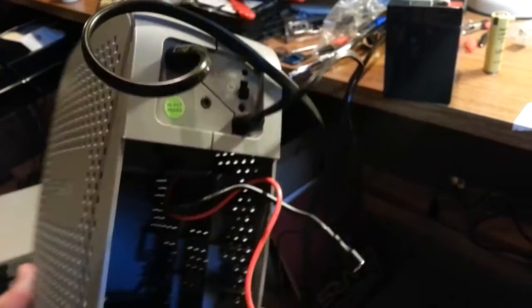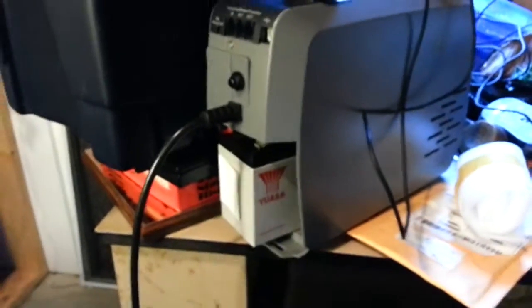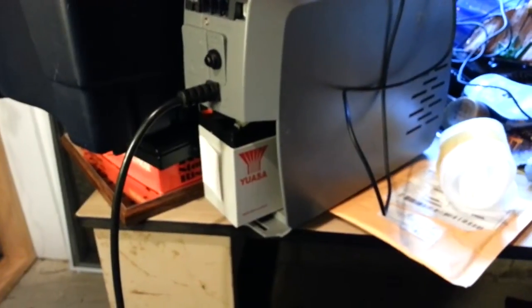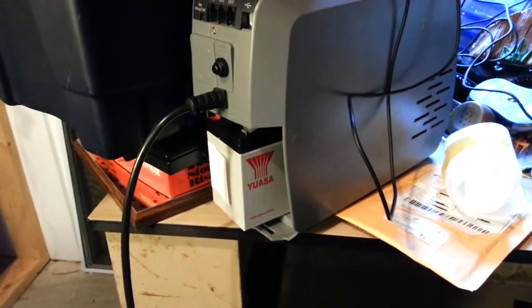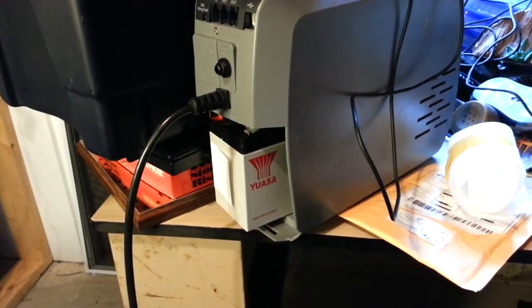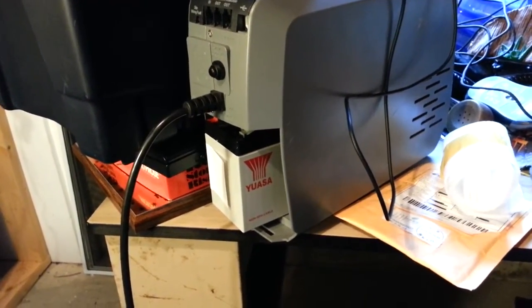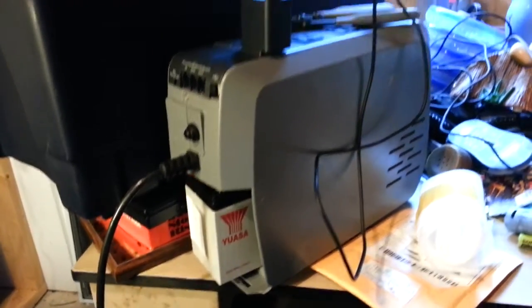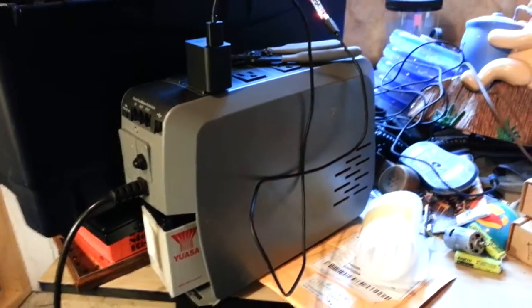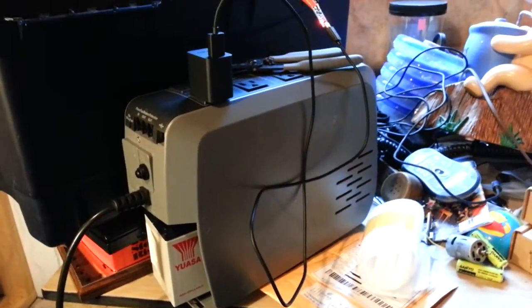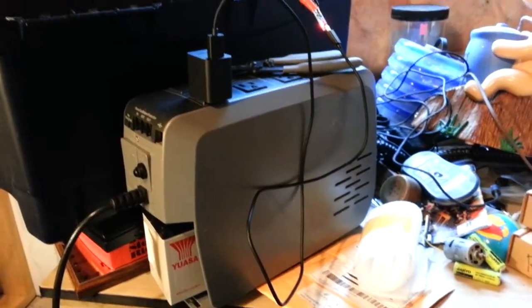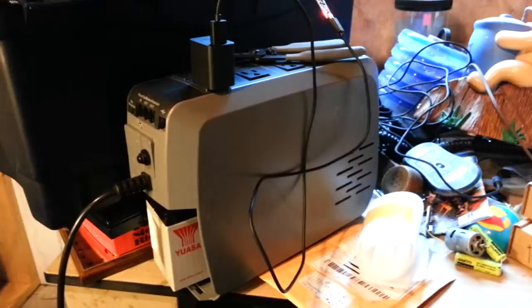That is the battery you can see in here. It was holding a voltage of 12 or better, so I hooked it up and the UPS started right up.